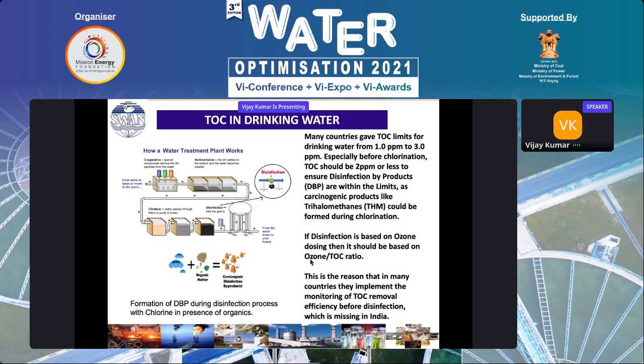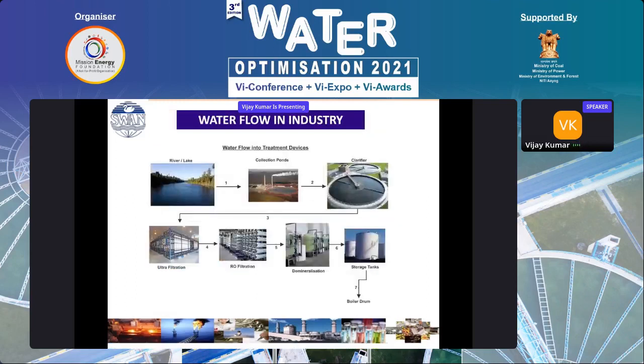Similarly, people are doing ozone dosing. The amount of organics will define the amount of ozone to be dosed. That is very important for effective disinfection. So normally, in any drinking water treatment, you see coagulation, sedimentation, filtration, then disinfection and distribution. In all these areas, TOC is getting removed. So that's where you need to understand.